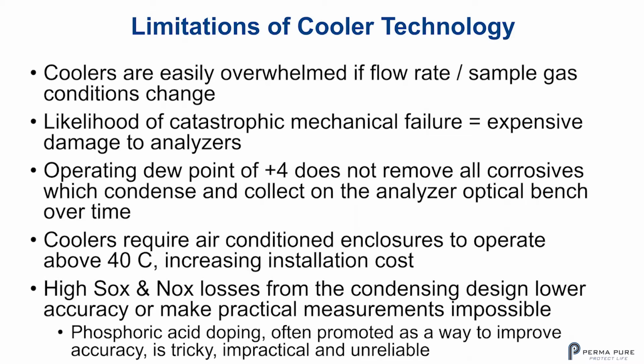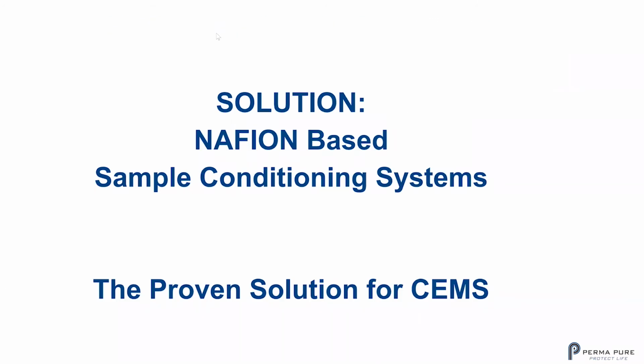There are some manufacturers that are promoting phosphoric acid doping as a way to improve accuracy, but it's tricky, impractical, and unreliable. It needs a lot of hand-holding to make sure that your phosphoric acid is enough. You have to constantly watch the system. It is really not a practical alternative. So the solution is Nafion-based sample conditioning systems, the proven solution for CEMS.